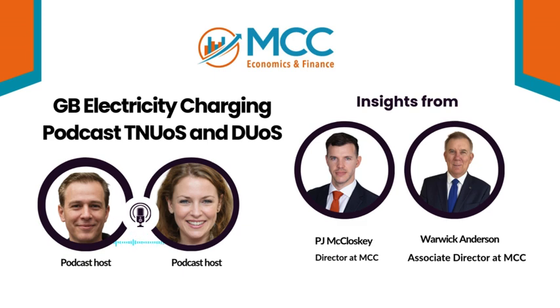Exactly. And just like with generators, TNUoS also has that residual charge for consumers. Right. It covers the rest of the costs that aren't about location. So it's like a service fee in your bank account. Yeah. Now for DUoS, the charges for consumers are calculated using either CDCM or EDCM, depending on their voltage level and usage. Right. EDCM is for the bigger users with those custom charges. Yeah, and CDCM puts people into categories with those standardized tariffs.